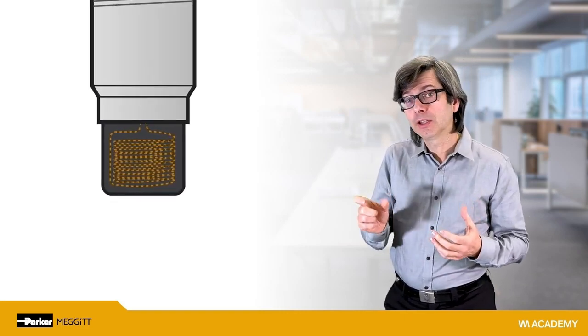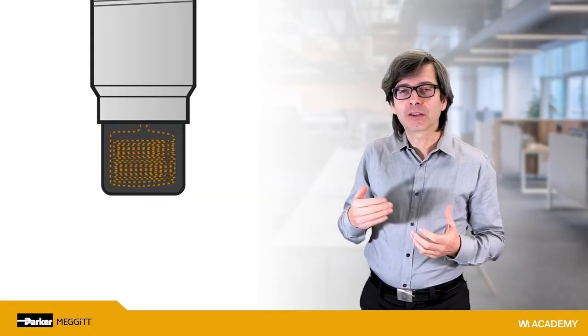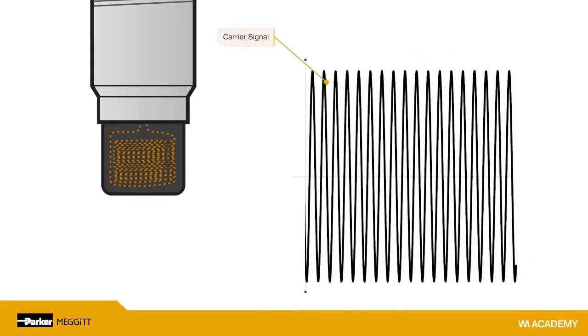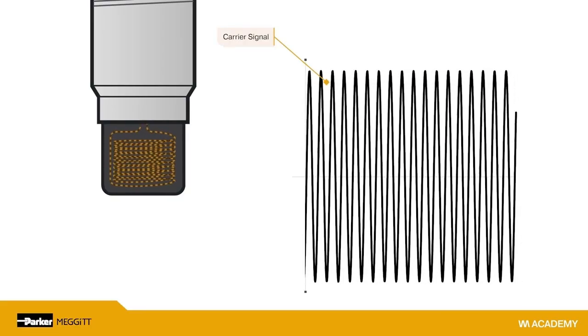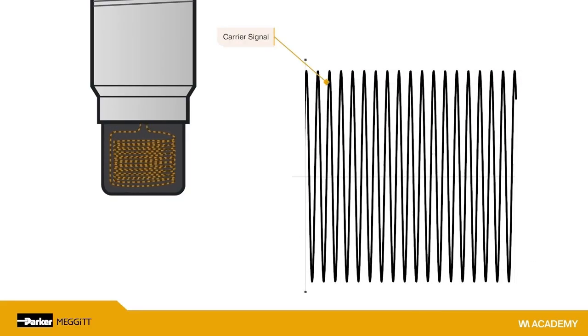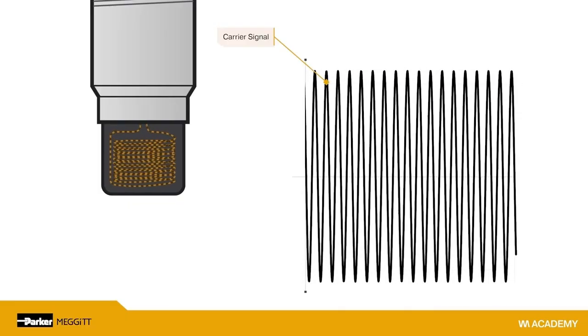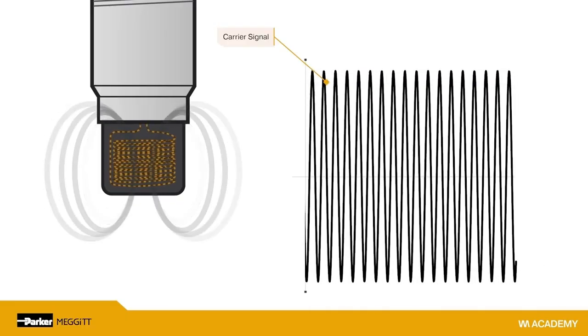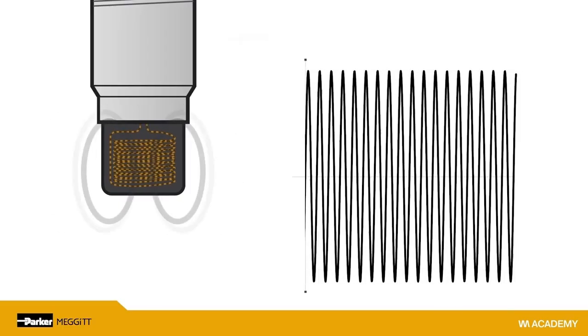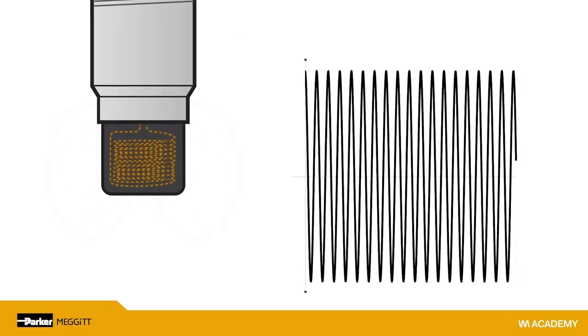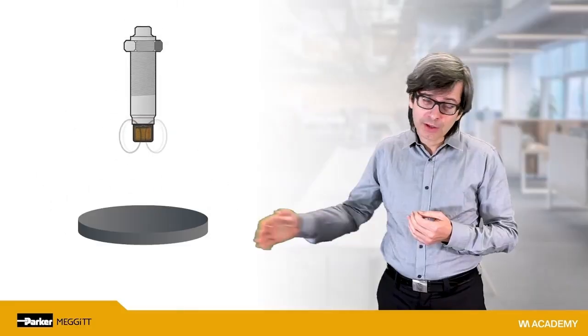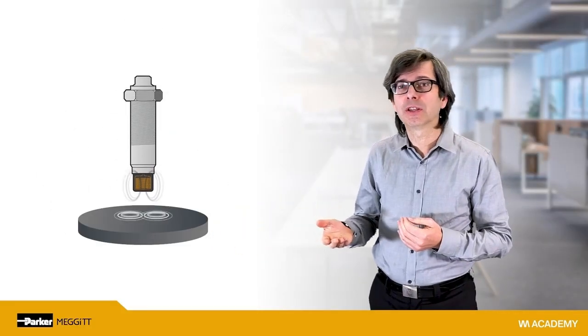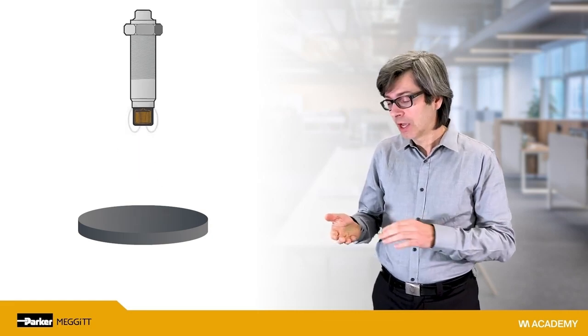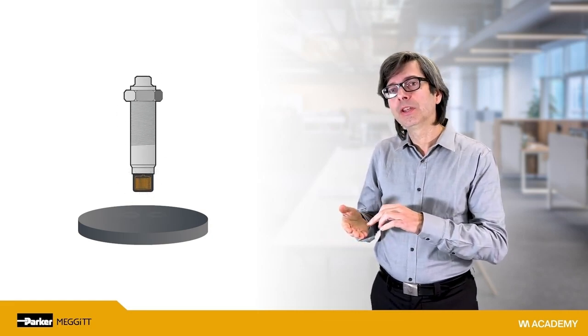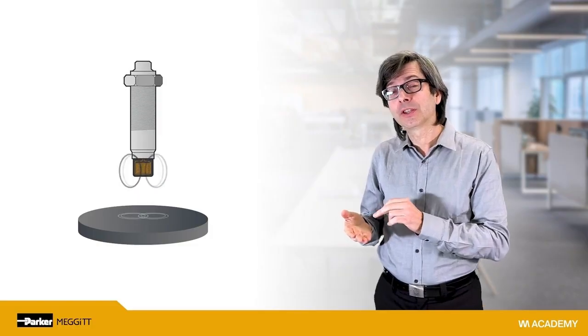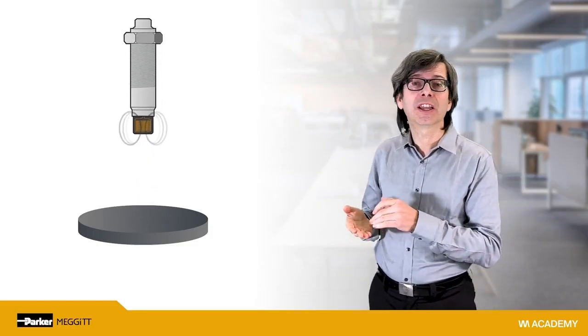That coil inside the tip is excited by an electrical sinusoidal signal called the carrier signal, which is an electrical signal of high frequency, in the order of megahertz. When that carrier signal goes through the coil, it emits an electromagnetic field in front of the sensor. And then when a target material crosses that electromagnetic field, an electrical current will be induced on the surface of the target material. This electrical current is called eddy current.